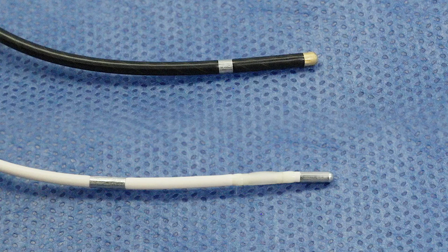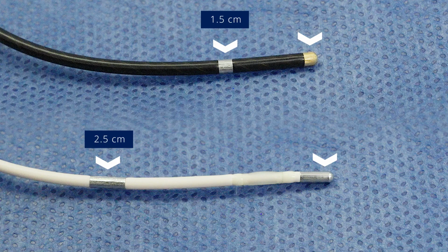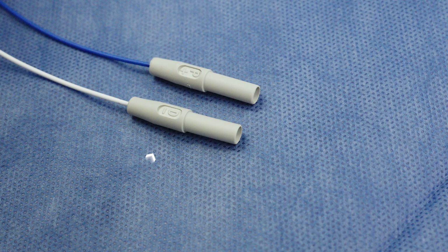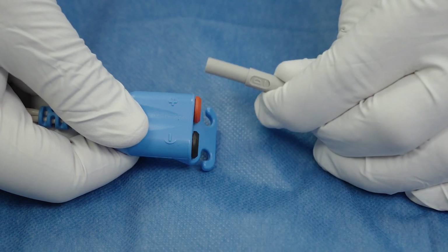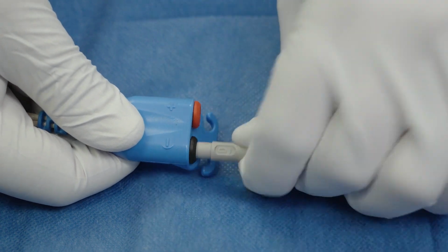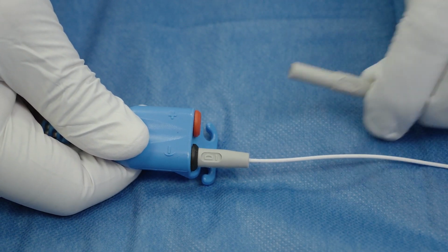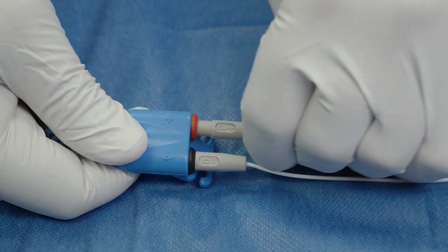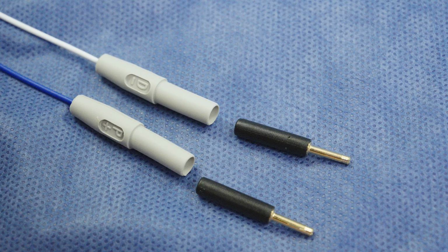It is available with 2 configurations with bipolar platinum electrodes located at the tip and a second platinum electrode at either 1.5 cm or 2.5 cm. The negative electrode jack marked D for distal must be connected to a negative terminal of an external pulse generator. The positive electrode jack marked P for proximal must be connected to a positive terminal of an external pulse generator. The proximal end of the catheter includes 2 recessed shrouded electrical connectors which mate directly to most pulse generators and are identified on their connecting cords according to electrode position. Reusable 2 mm socketed pin adapters are included to be used as needed.